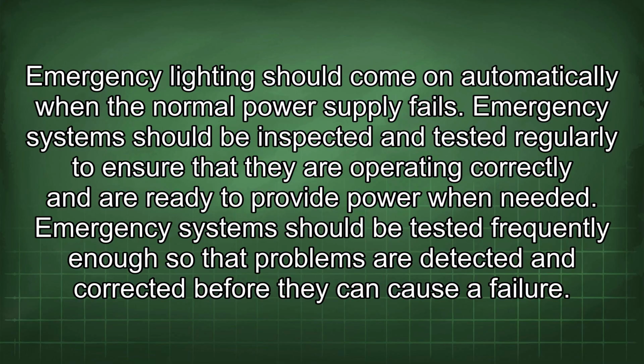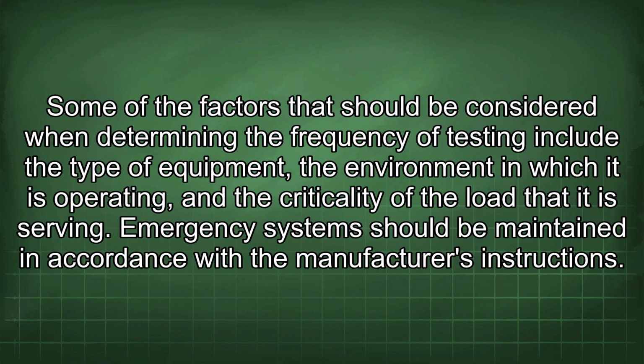Emergency lighting should come on automatically when the normal power supply fails. Emergency systems should be inspected and tested regularly to ensure that they are operating correctly and are ready to provide power when needed. Emergency systems should be tested frequently enough so that problems are detected and corrected before they can cause a failure. Some of the factors that should be considered when determining the frequency of testing include the type of equipment, the environment in which it is operating, and the criticality of the load that it is serving.